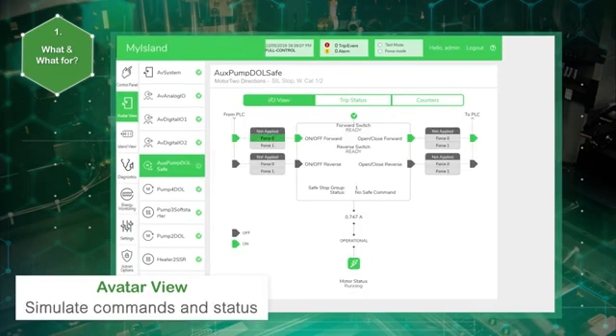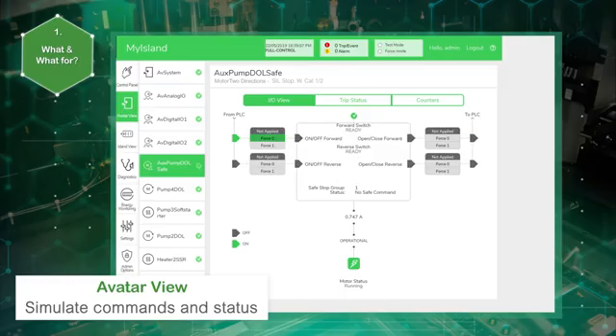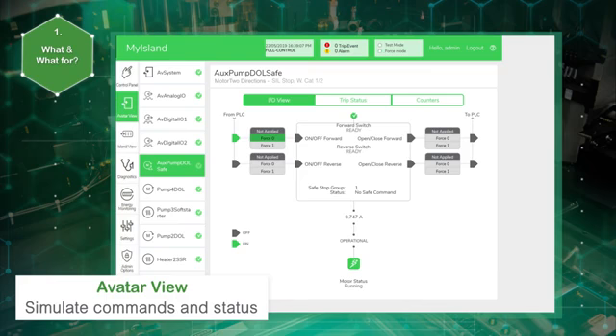In order to ease diagnostics, the force mode allows to simulate commands from the PLC or status updates to the PLC. Once the force mode is activated, the force mode indicator flashes red and the power LED of the bus coupler flashes yellow.